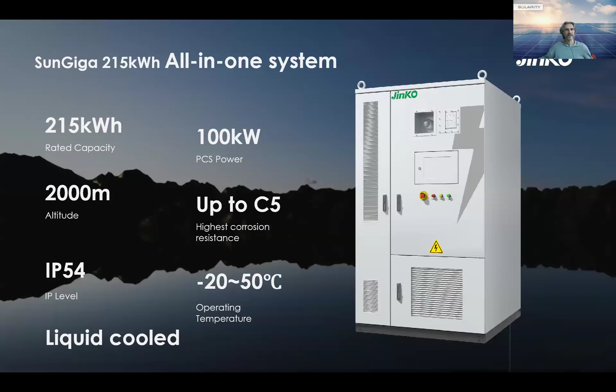The DC part is 5 packs reaching a 215 kilowatt-hour capacity, with a PCS with 100 kilowatt output power at 400 volt. It's IP54, so it can be used in outdoor environments up to C5 corrosion grade, which is the highest grade applicable for this kind of enclosure. And it's liquid cooled. This is the last bullet point in this chart, but probably the most important, because the safety system is one of the most important topics for BESS systems.